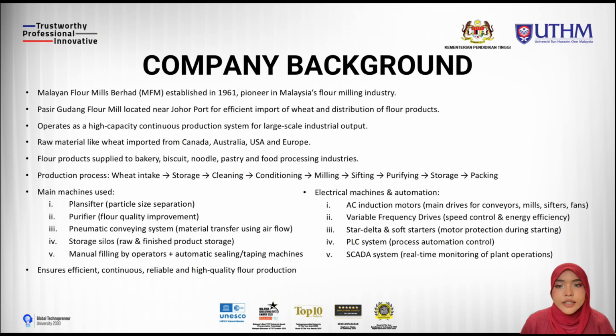From an electrical engineering perspective, the plant relies on AC induction motors to drive equipment such as roller mills, conveyors, sifters and fans. Variable frequency drives are used to control motor speed and improve energy efficiency, while soft starters and star-delta starters protect the motor during startup. The entire production process is automatic using a PLC system and monitored through SCADA, ensuring efficient, reliable and continuous flour production.